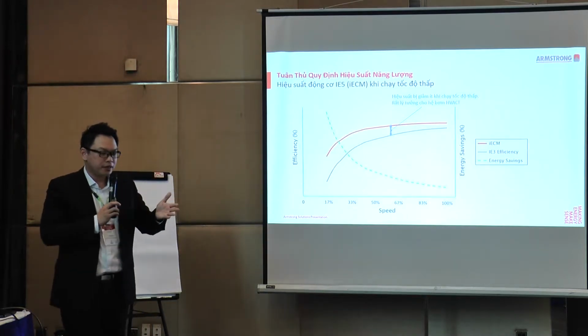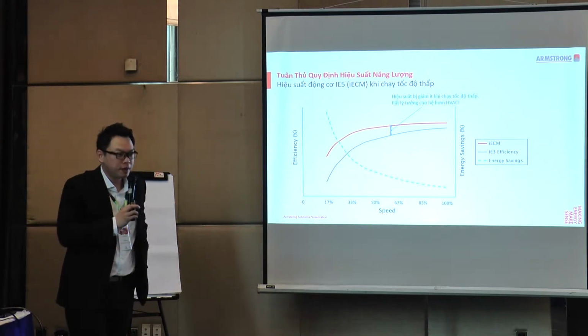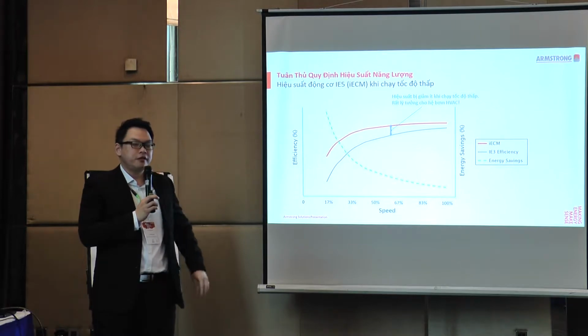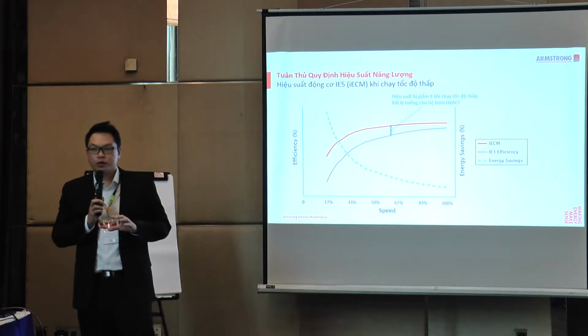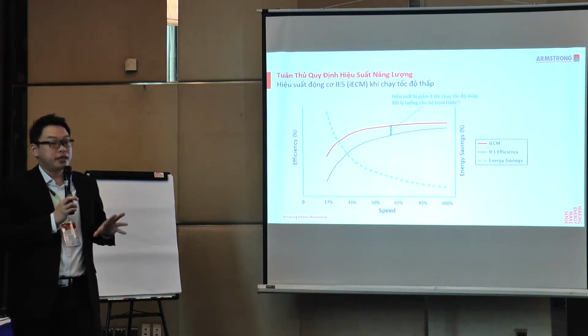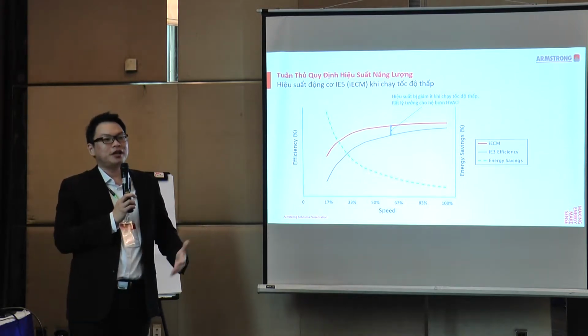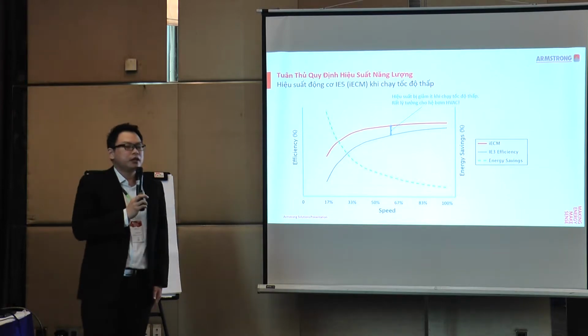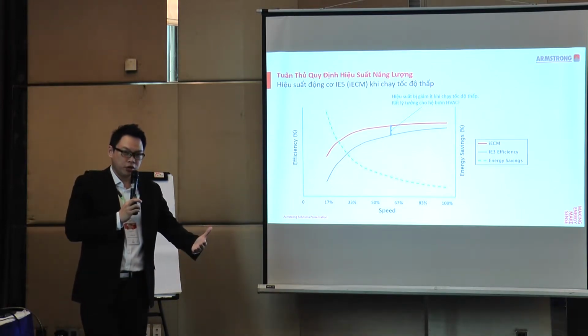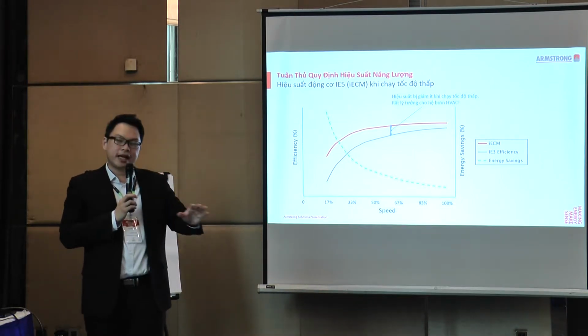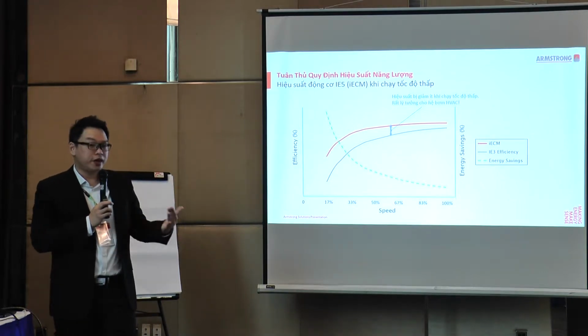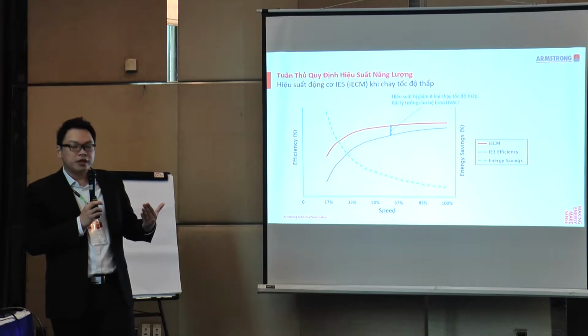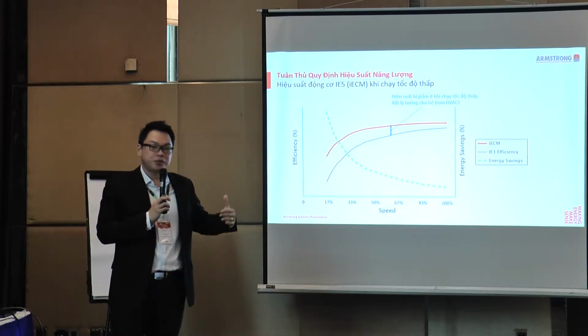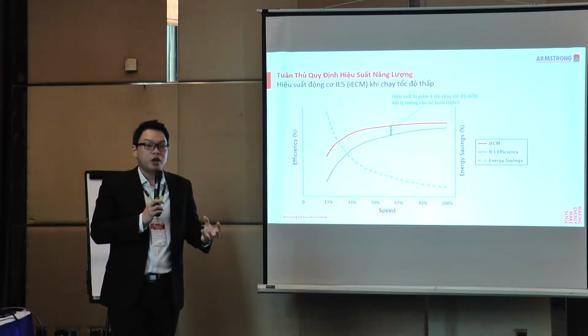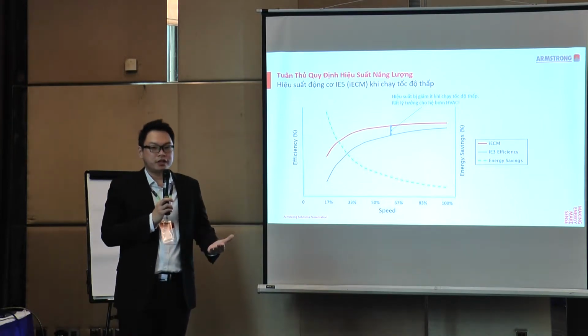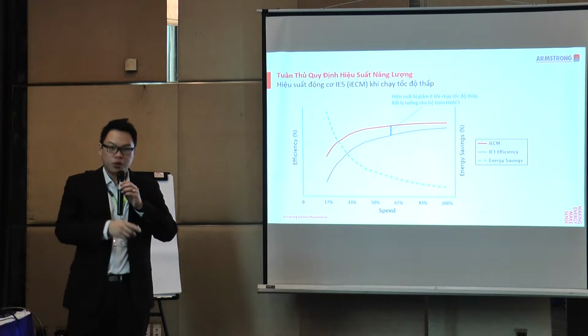Later on, my colleague Ronnie is going to introduce our Generation 5 Tango pumps, which are available up to 10 horsepower. These 10 horsepower motors are IE5 ready. I know right now IE4 is pretty common, and when IE5 becomes more prominent in the market, we do have the solution. What this graph is telling you is that with our IE5 ready motors, there's going to be less drop-off in efficiency at lower speeds. Why is it able to do this? Because we're using a permanent magnet motor. That means the slip loss is less, giving you a higher efficiency, even at lower speeds.